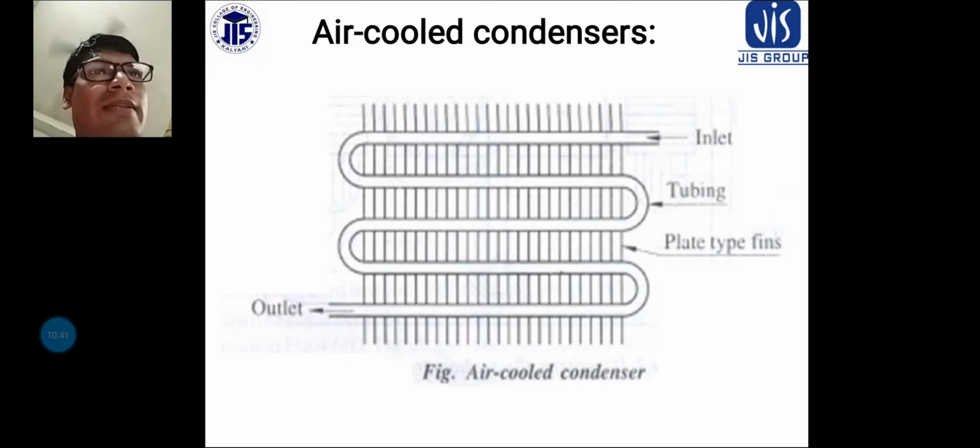The condenser coil is of the fin type, and the fins in such a coil are closely spaced, about 5 to 7 fins per centimeter. The space between fins gets choked with dirt and lint. Therefore, to obtain optimum capacity, the fins should always be kept clean.